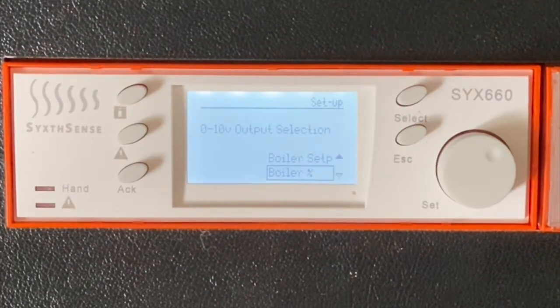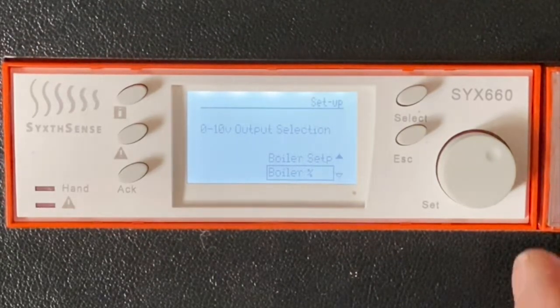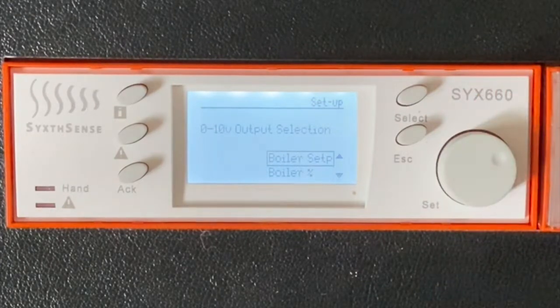And that could also be used to drive a boiler directly. We don't have to use a sequencer. That would only be for multiple boilers. If there was one boiler that could accept a 0 to 10 volt signal, we could drive that boiler directly, just using that as a demand signal. Equally, if the boiler is compatible with it, we could send a 0 to 10 volt signal as a boiler set point, where we can scale the 0 to 10 volt output to be reflective of the actual flow temperature demand. So that's another unique feature of the SYX product in this category of products on the market.